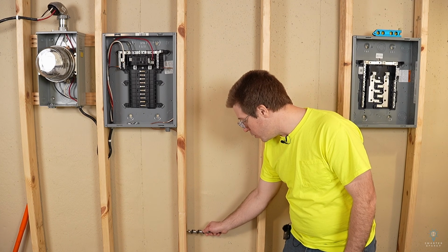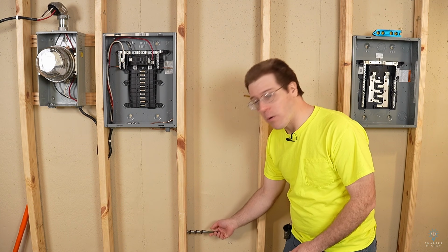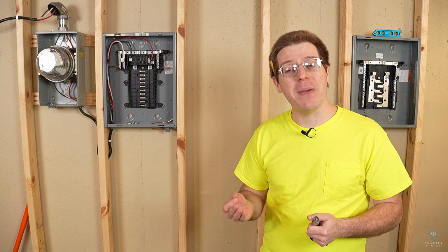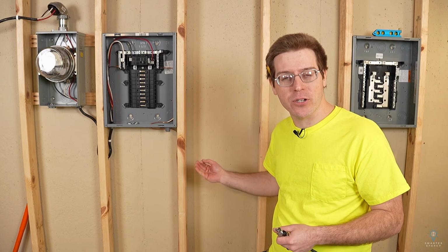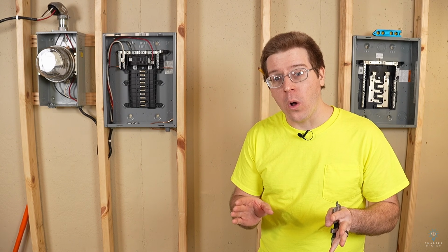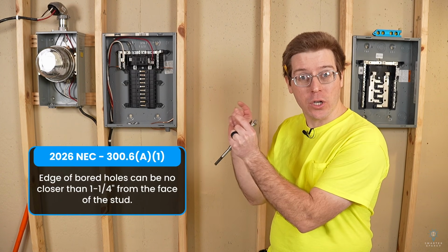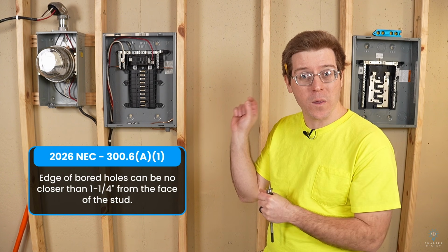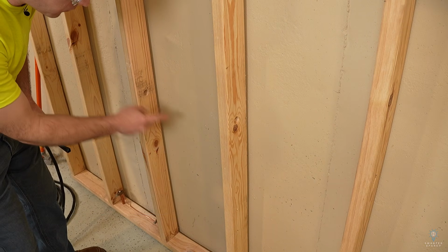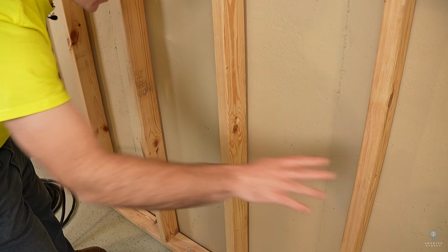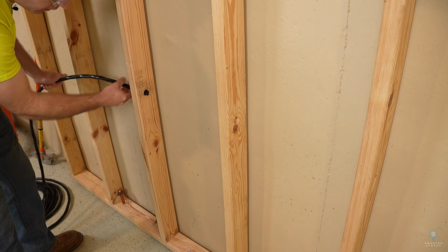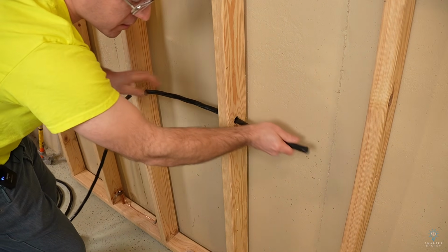Otherwise, we would just use a drill and drill our holes through the studs. Again, making sure we stay within the center of the stud. The edge of our hole can't be any closer than 1.25 inches from the front of the stud or the back of the stud. So as we can see here, there are already holes drilled through these studs. So I'm gonna go ahead and run the feeder wire straight through our studs here.